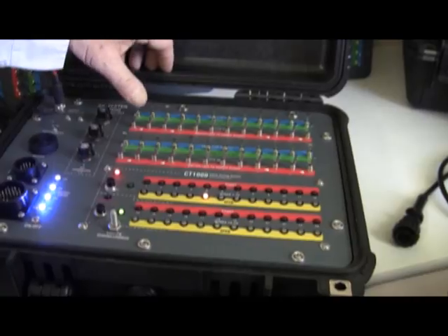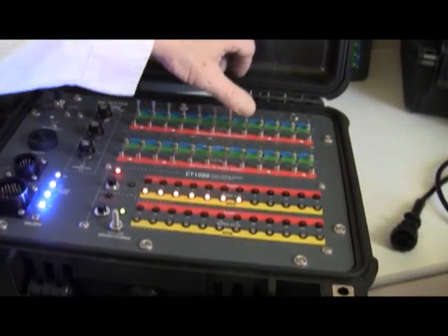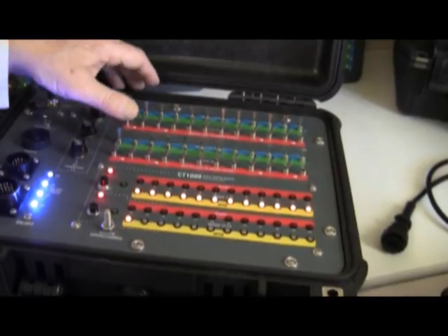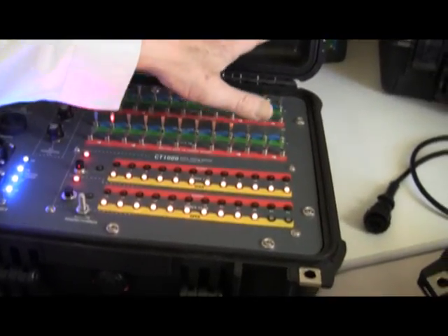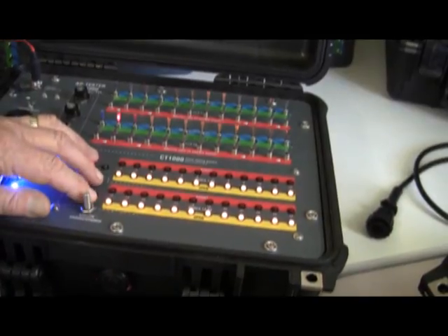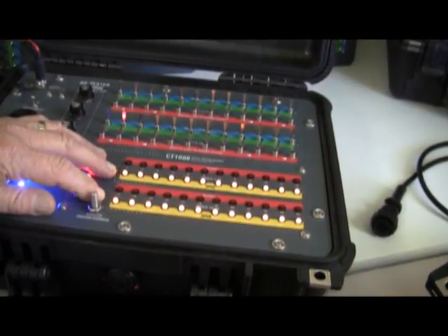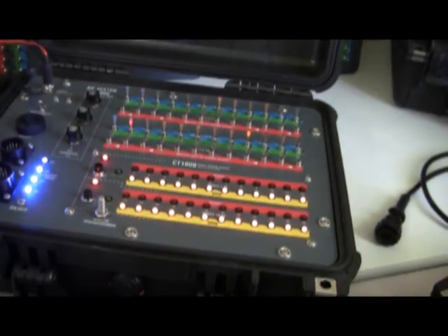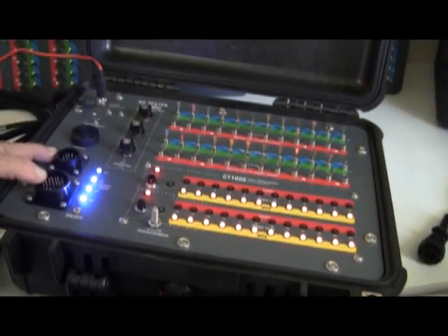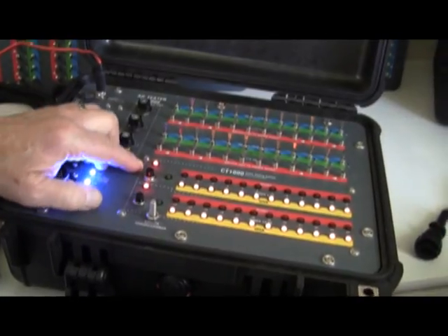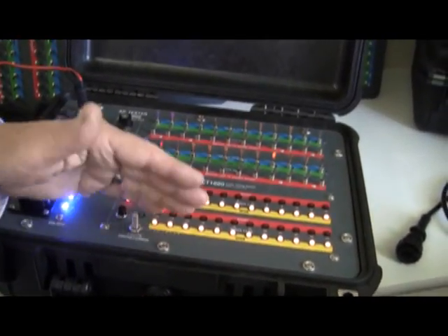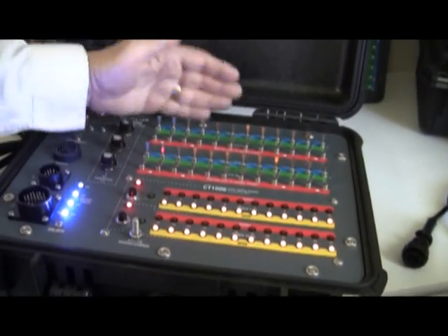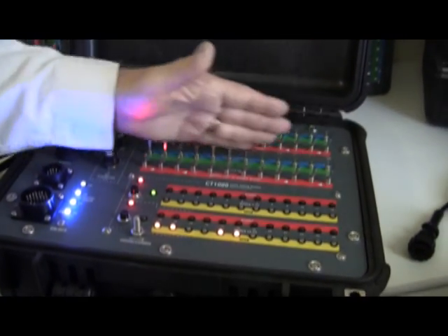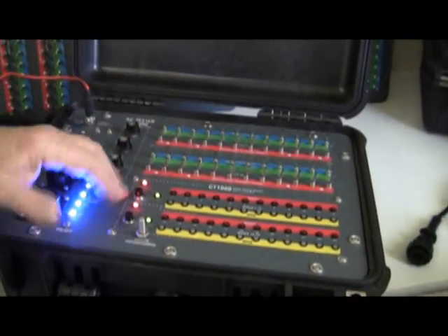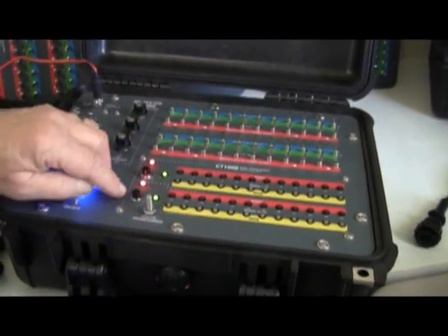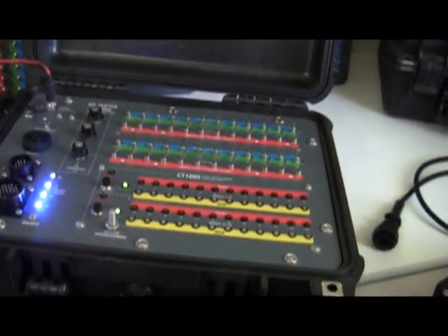For a quick test of the unit, if I turn on all the wires associated with all 24 rows, you'll see all 24 wires showing as open. That makes sense since both groups are open - there's no connector plugged in, nothing hooked up. So we have an alarm condition, and we can't reset it until all these issues go away. Let me kill it real quick - now our all-okay light comes back on, and we can reset each group.